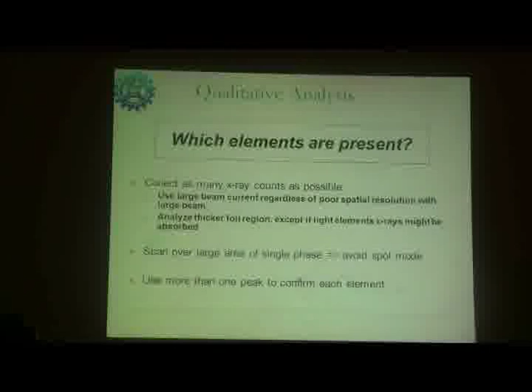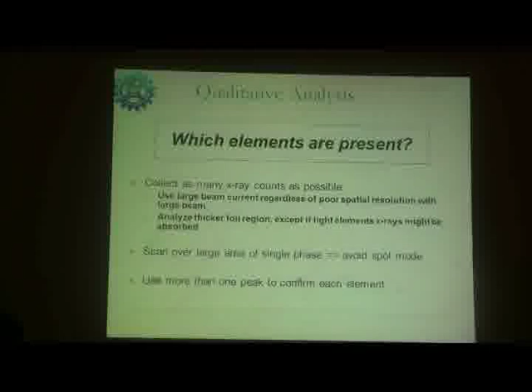So that's how you have the scan generator control, then you can do a lot of features. Suppose I took a secondary phase like this, which is something different. I can position the beam on this area and do the EDS analysis, so that I can know what elements are present in that particular secondary phase. So you can do all sorts of things using EDS.